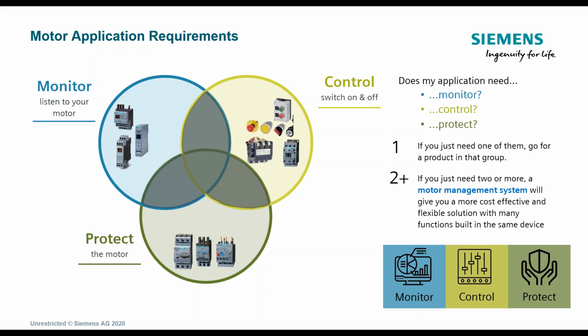You have to protect that motor. Heat and overcurrent is a big enemy to the motor. You want to protect it. You want to keep it running efficiently and properly. Of course, you want to have some PMs on it to where you have to grease the bearings or maintain whatever the motor is connected to, a conveyor belt, a fan, etc.